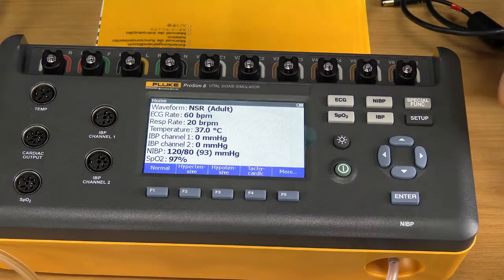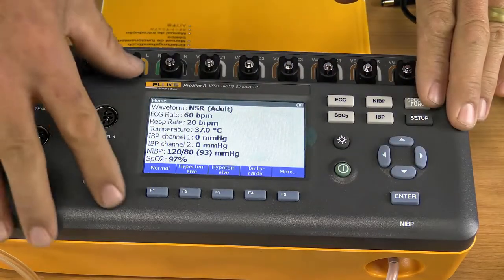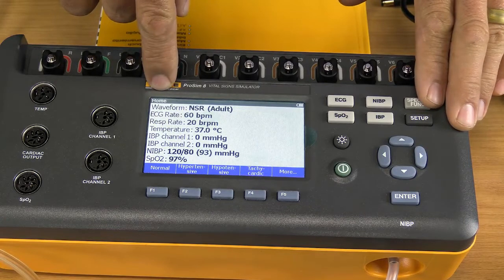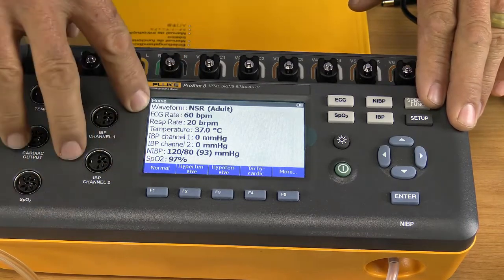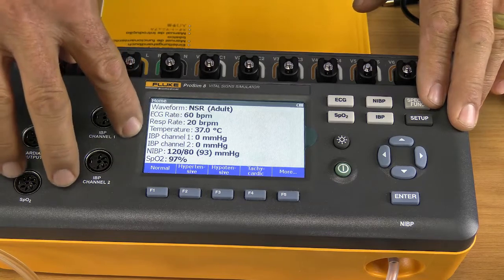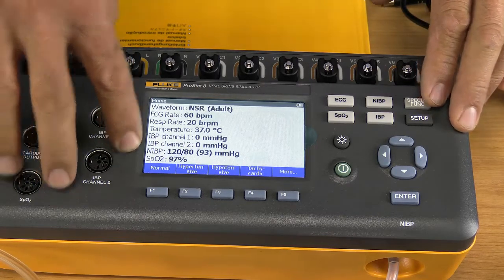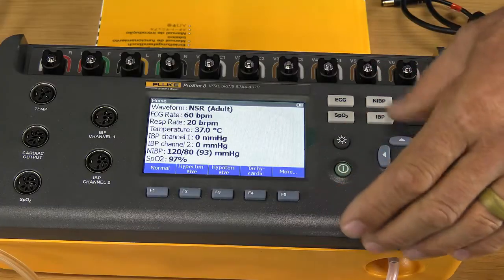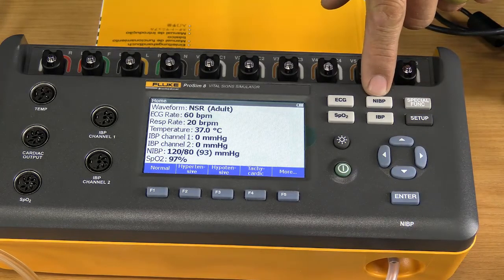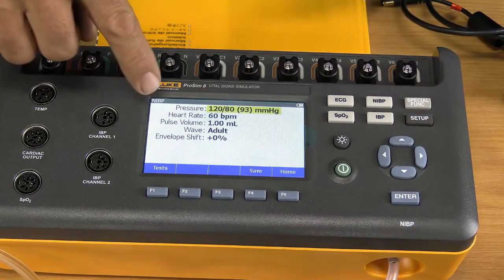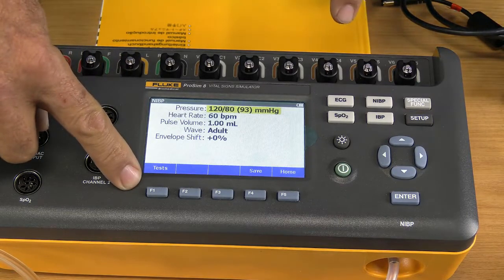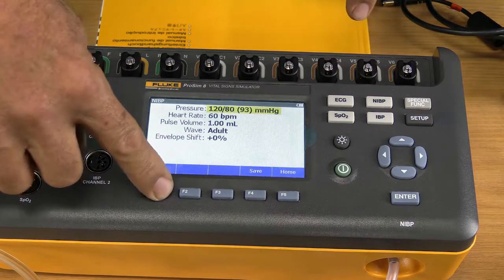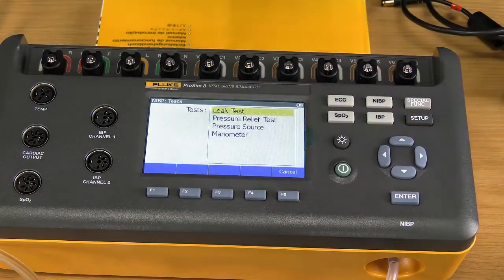Okay. When we go down to our simulator, when it's switched on, it comes into the home screen, as you can see here, where we've got a normal patient setup with its ECG, respiration, temperature, IBP, and NIBPs. But the test we want to do is we want to send a static pressure to our monitor. So in order to get to that, we have a NIBP function. You can see this NIBP button here. If you press that, you'll see that at the bottom here, function 1, it says test. If I go to test, I've got 4 tests that come up here.